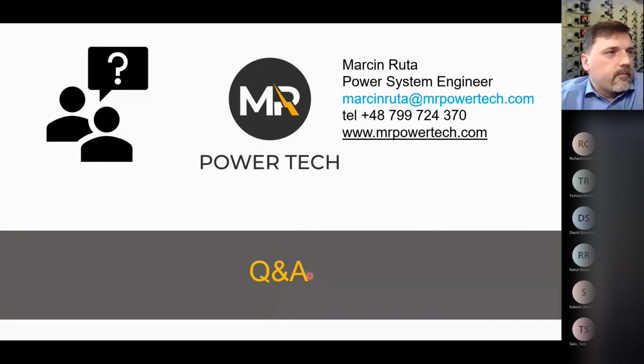What is? All switchgears designed in accordance with IEC standard, which doesn't require additional PPE for operation in country. Is this correct understanding? Well, actually, no. So, as a rule of thumb, you might say that everything requires PPE, some sort of level. Is it arc flash PPE, or PPE against electrical shock hazard? It very much depends what you are doing.